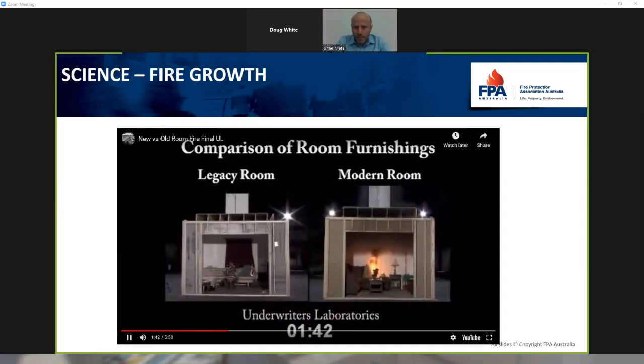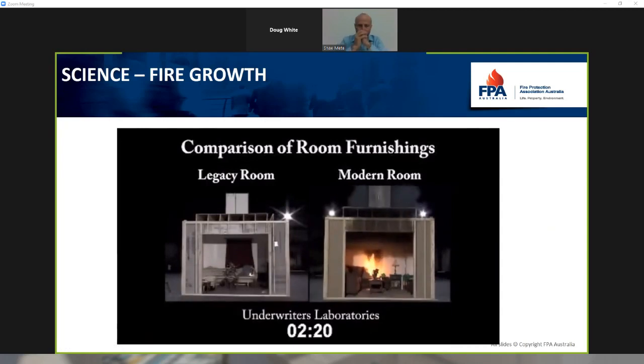Let's get this to 2 minutes. You can see that if there wasn't an opening here, the compartment would have filled fully with black smoke. It's pretty much accepted that if you were still in the room at this point, you're probably not coming out alive. You have to keep in mind that it's very unlikely that brigades would be arriving in this kind of time frame.